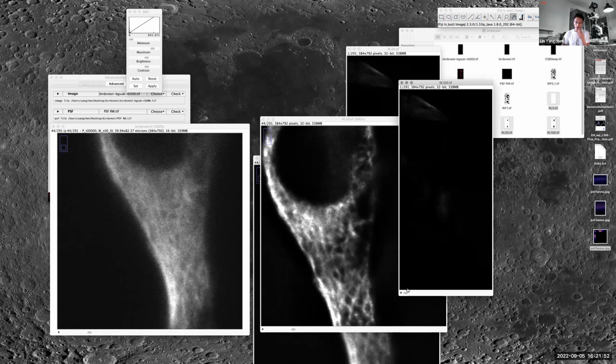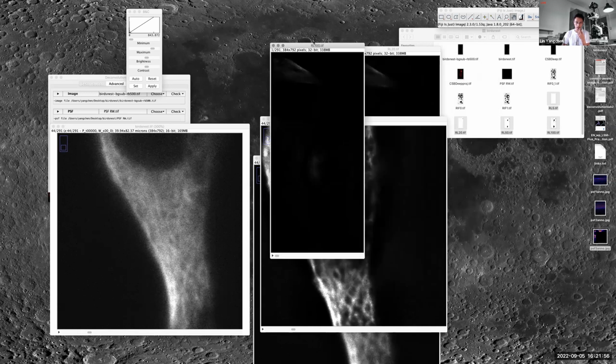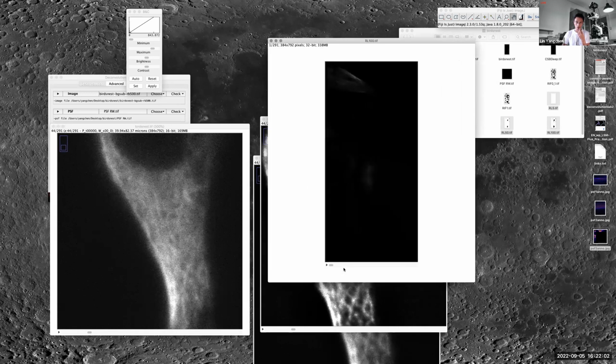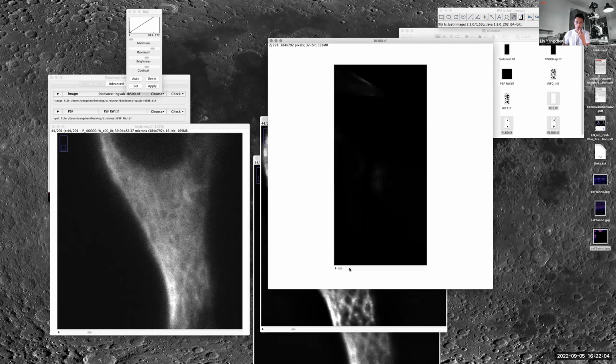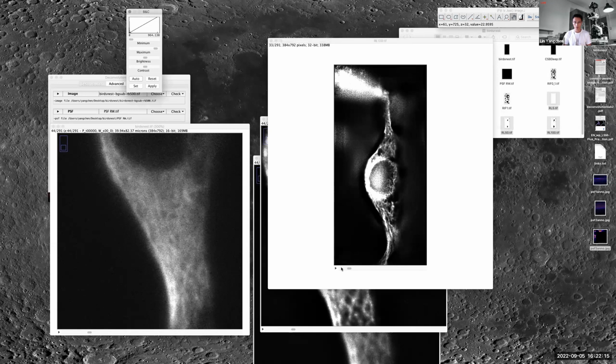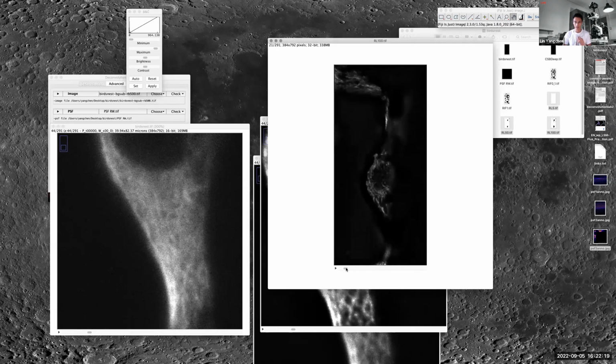An interesting artifact that I encountered when I went up to 100 iterations, and I can show you, is the so-called blooming artifact. If you go through the slices, the rest of it is fine until you get to one particular slice, slice number 33.